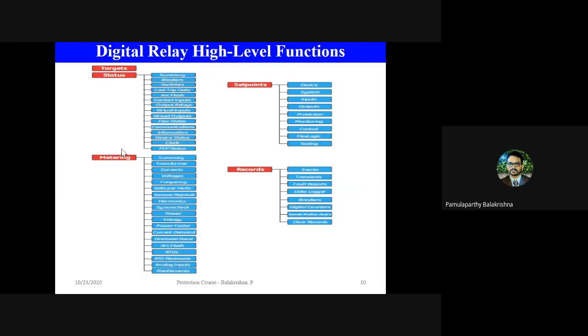Okay, so the second major function is the metering, which is nothing but the analog values. By taking these voltages, currents and temperature from various signals from the field, you compute further data like power, energy, harmonics, power factor, demand. So all those things that you are computing, the analog values, are represented as the metering values, which form the input to the protection function. So apart from the standard signals coming in, the computed signals are also used for protection purposes.